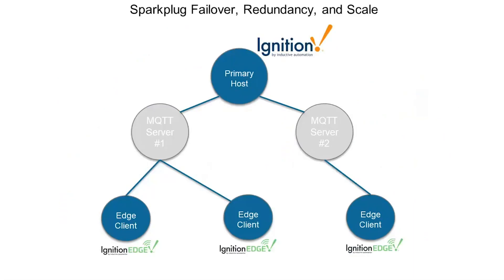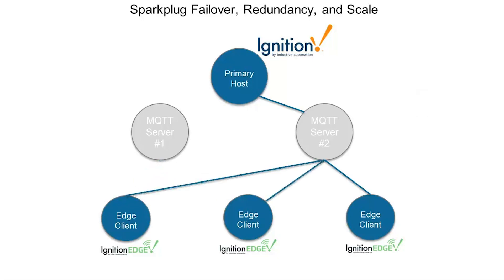Looking at Sparkplug's definition of failover, redundancy, and scale — in an operational system, we need one application issuing commands as the primary host. In this architecture, Ignition is the primary host with two available MQTT servers and three edge clients connected. If we lose our network connection from the primary host to MQTT server one, we want to tell those field clients that the primary application is no longer connected to that server, so they disconnect and connect to another available MQTT server in the infrastructure that is connected to our Ignition gateway.